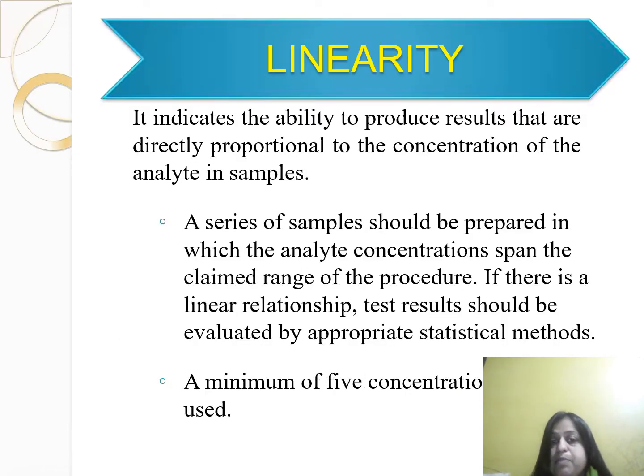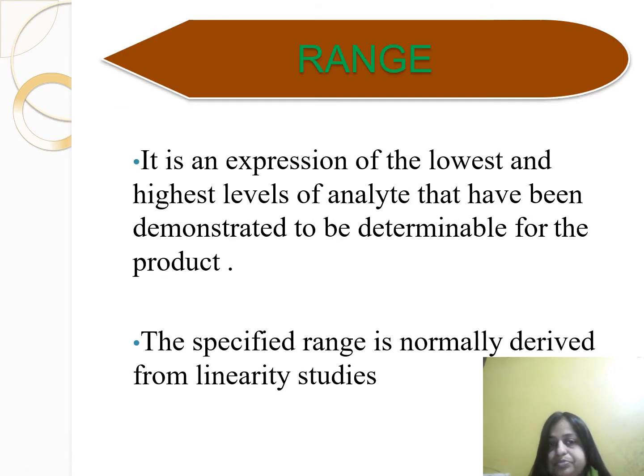Linearity indicates the ability to produce results that are directly proportional to the concentration of the analyte in the sample. A series of samples should be prepared in which the analyte concentrations span the claimed range of the procedure. If there is a linear relationship, test results should be evaluated by an appropriate statistical method. A minimum of 5 concentrations are used.